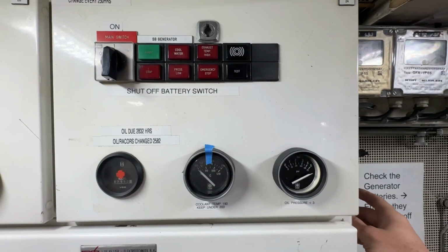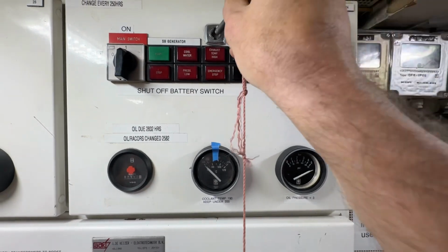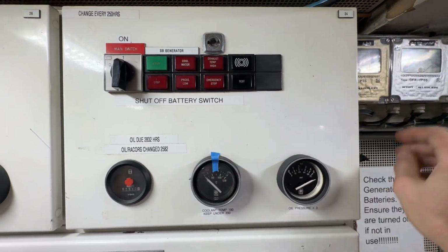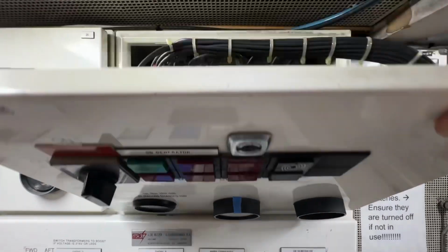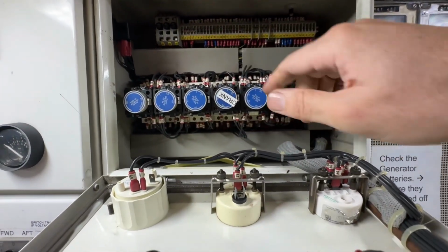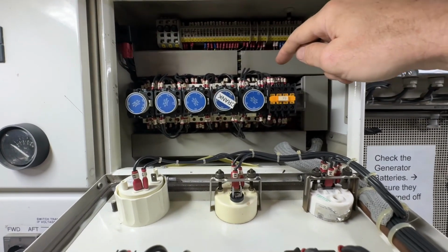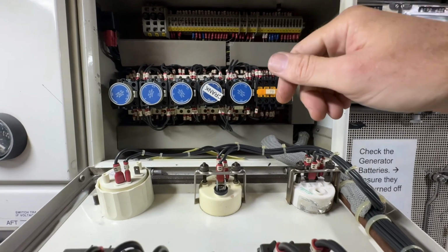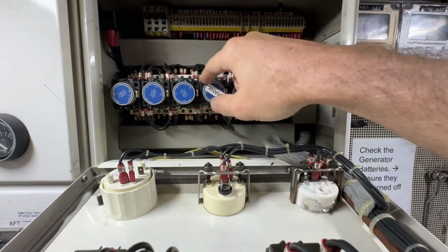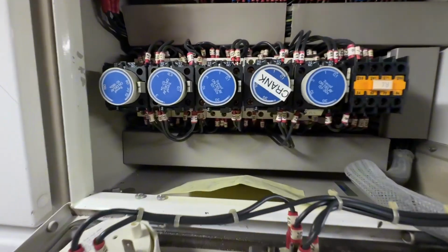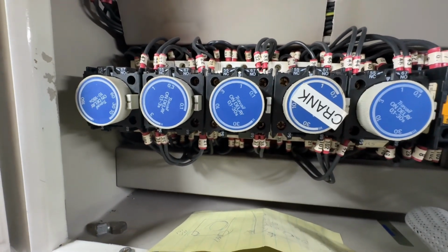So this time let's do the same thing, but we'll go ahead and open this panel, and take a look at the relays back here and see how they're working. Here's the 5 delay timers and the 5 relays. I keep calling them relays, but they're really contactors, just like on a home air conditioner. These are going to fire off one by one, and I'll just reach under here and hit that same start button, and we can watch the little chick, chick, chick as it goes.